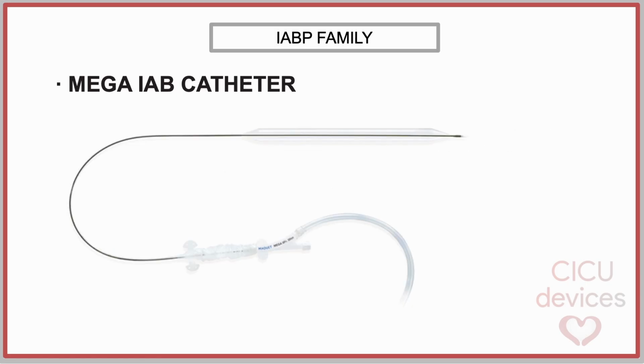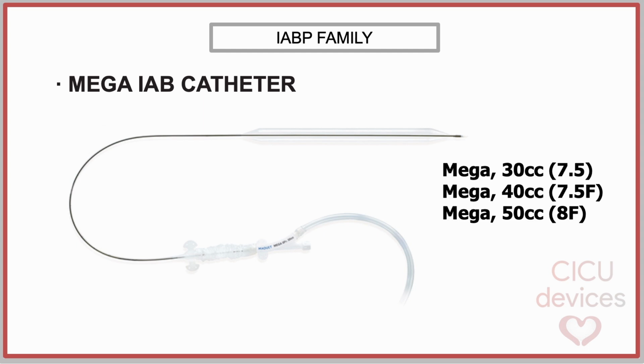The Mega IABP catheter is designed to provide enhanced hemodynamic support through the use of larger balloon volumes, making it particularly suitable for taller patients or those requiring greater diastolic augmentation. Like the Linear catheter, the Mega series incorporates a conventional fluid-filled central lumen for continuous aortic pressure monitoring. The Mega catheter is available in 3 balloon sizes. The 30 milliliters model is intended for patients shorter than 152 centimeters and has an external diameter of 7.5 French. The 40 milliliters catheter is recommended for patients between 152 and 162 centimeters, with an external diameter of 7.5 French, while the 50 milliliters version is designed for patients taller than 162 centimeters, with a diameter of 8 French.